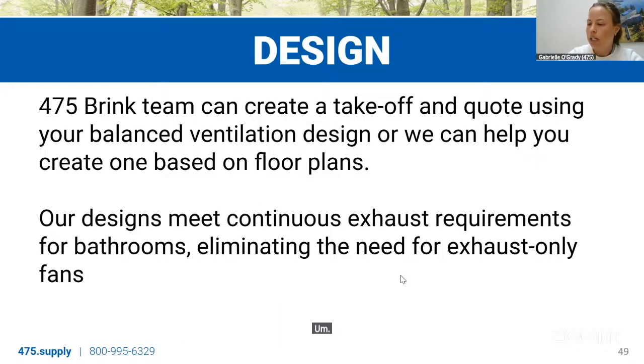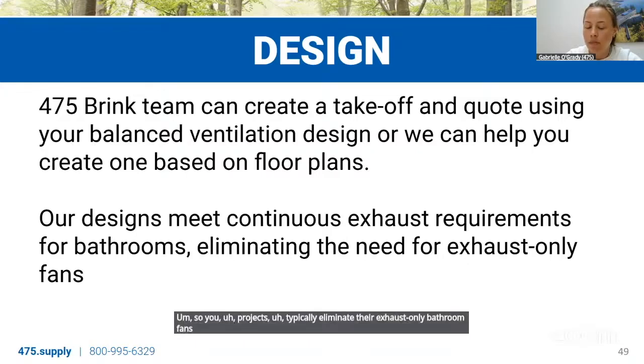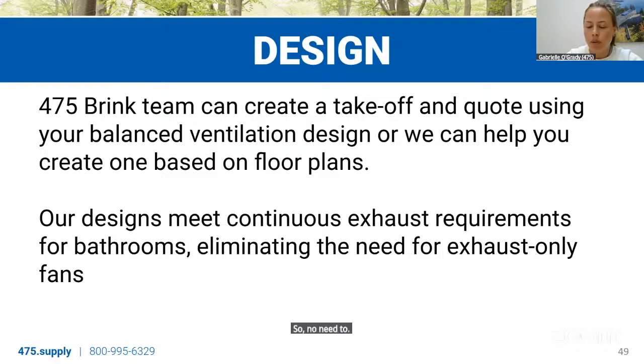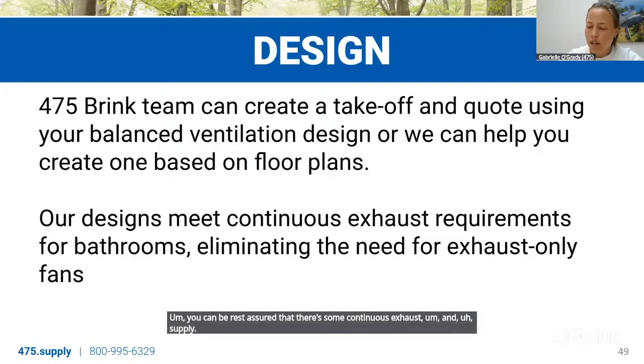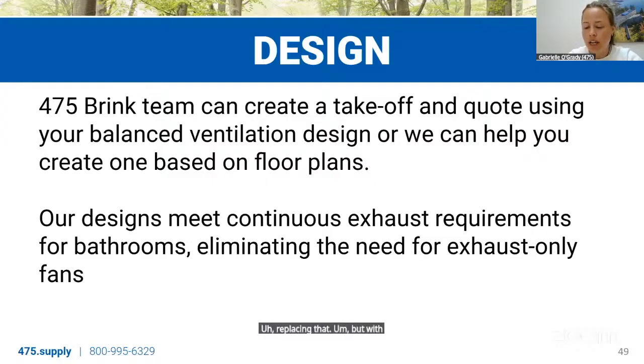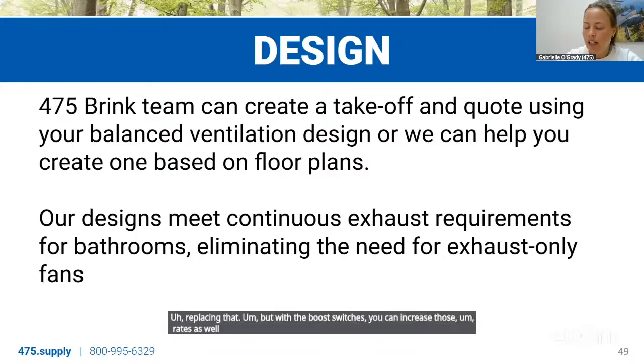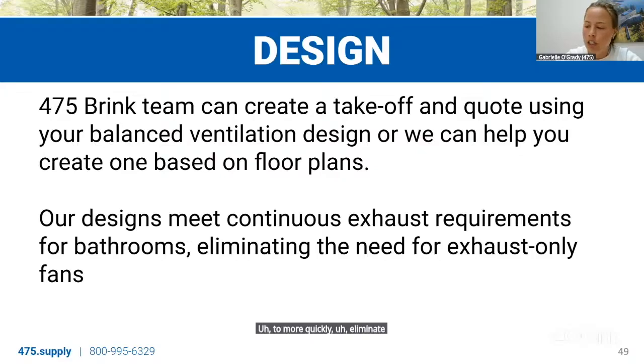And a special note here, when also planning out a home, the Brink ERV systems do meet continuous exhaust requirements, meeting code requirements. So projects typically eliminate their exhaust-only bathroom fans, and do so very successfully. Not only are they continuously exhausting air from the bathrooms, and that air is being replaced, but there's also no need to worry that occupants might forget to turn on an exhaust-only fan. You can be rest assured that there's some continuous exhaust and supply replacing that. But with the boost switches, you can increase those rates as well, to more quickly eliminate the moisture in the bathrooms.